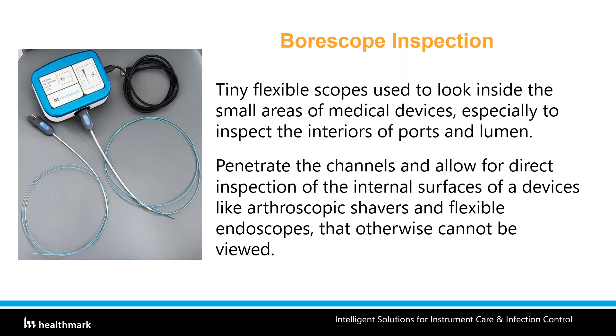And if not, when you look over time, you see there are some issues. For example, over time, you see there is some junk and rust here. I don't know what these are. Probably they are stuff that shouldn't be within the endoscope. And here, sometimes the outer shield, that plastic rubber, if you bend it, it probably could pop back up, but those clear tubing could get damaged. So if you look at these here, once you get that, it's really difficult to run the brush through these areas and clean them.